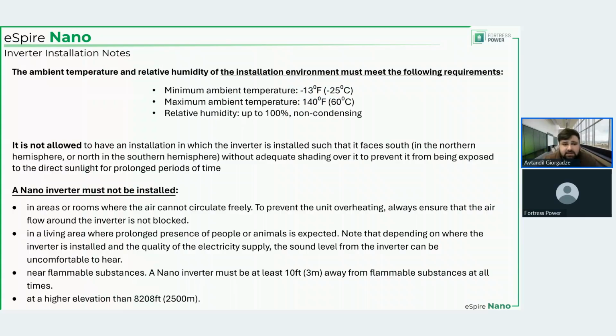But since this is an indoor installation, I find it difficult to imagine an indoor installation in which the temperature falls below 4 degrees Fahrenheit. And even if it does, we're talking cell temperatures, not ambient temperatures. But for the inverter, because it's sitting outside and it does not have a dedicated enclosure and it's not heated or cooled via HVAC, it is very important to keep these temperatures in mind.